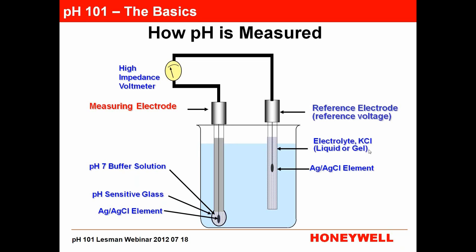We put the reference wire into a potassium chloride liquid or gel, which fixes the voltage potential at the reference electrode so it stays constant. As long as it's constant, it can be compared to the varying voltage of the measuring electrode. Without a connection between the measuring and reference electrodes, we have to add a porous liquid junction that allows electrical current flow between the measuring electrode through the process fluid and up to the reference electrode — through the gel electrolyte — so that current flows and you can see the pH at your instrument.